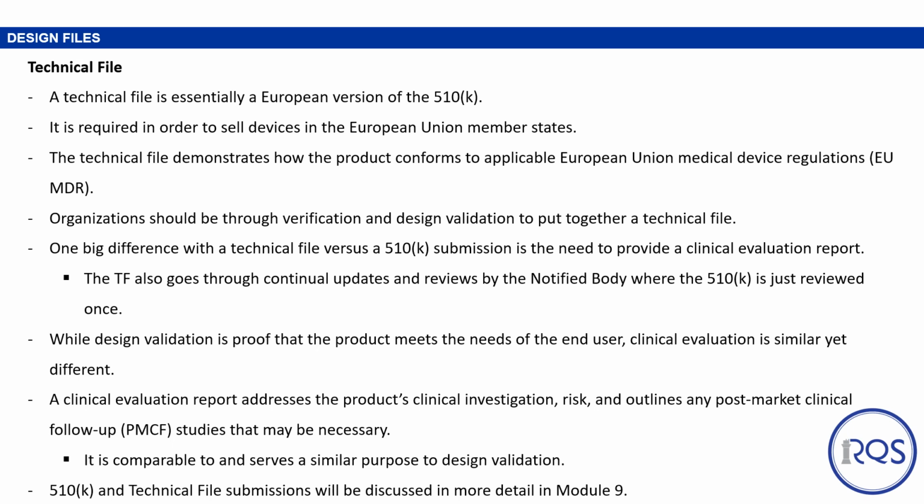While design validation is proof that the product meets the needs of the end user, clinical evaluation is similar yet different. A clinical evaluation report addresses the product's clinical investigation, risk, and outlines any post-market clinical follow-up, or PMCF, that may be needed. It is comparable to and serves a similar purpose to design validation. 510(k) and technical file submissions will be discussed in more detail in Module 9.